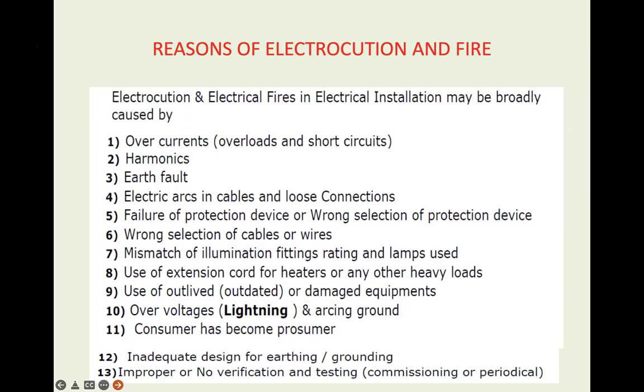You have to have some provisions to protect your systems against lightning and arcing grounds. Whenever you use solar PV at the rooftop, because now the consumer has already become a prosumer, they are consuming as well as producing the power. And because of this solar PV on the rooftop and the inverter used along with it, there is a change in the power factor. And because of the change in the power factor, the current drawn becomes more, even the DT core becomes hot.